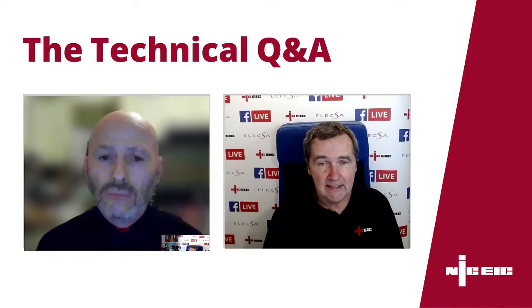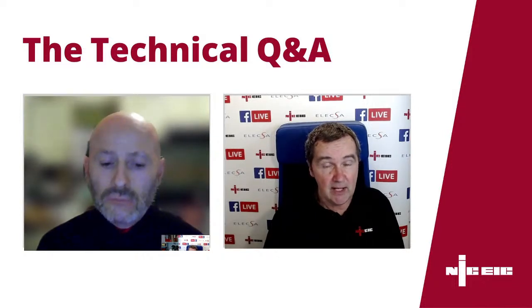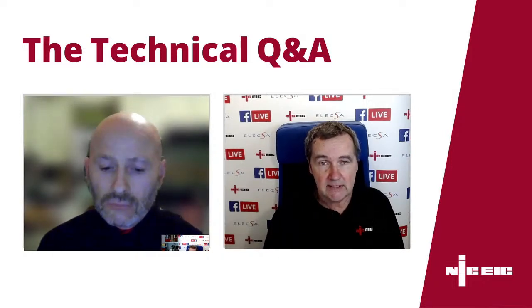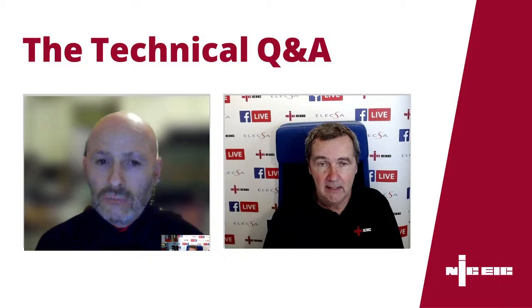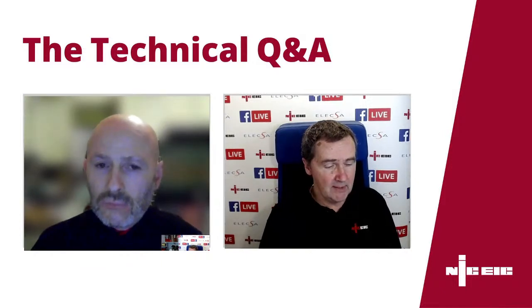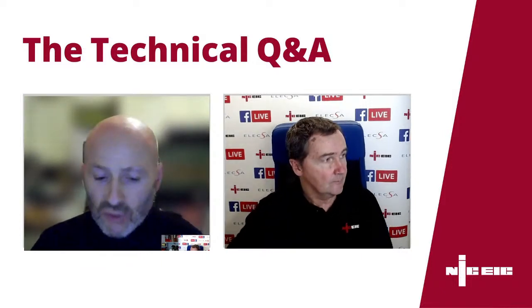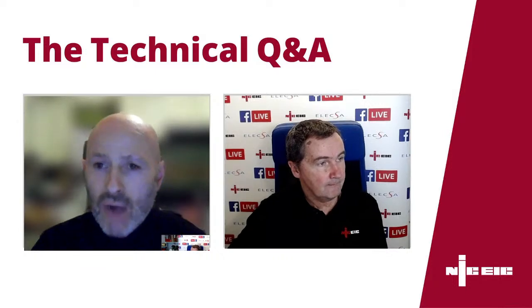So it really does depend on what the RCD is there for, whether it's additional only, in which case worst case scenario would be a C3. If it's for additional and fault, then worst case scenario would be a recommendation of a C2. Do you agree with that one, Dean? 100%. I'm just going to throw a regs number in there for those who want to take a note of it.